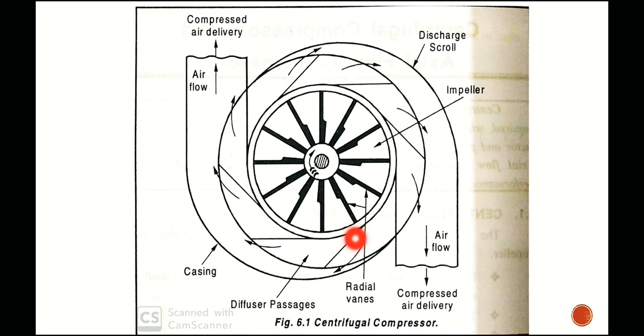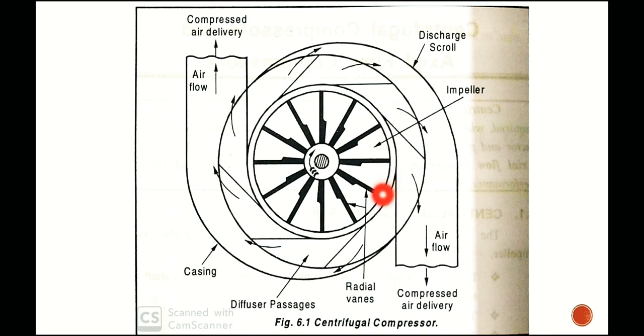As per the continuity equation, area multiplied by velocity is constant. So as the area increases in the diffuser, velocity decreases. The air entering the diffuser has high velocity; as the area increases, velocity decreases, and correspondingly the pressure increases.